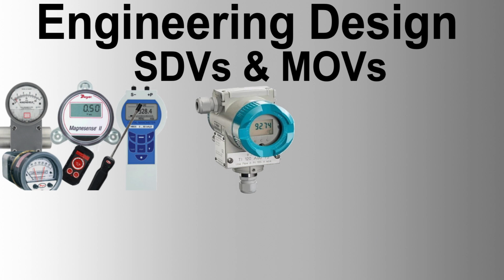Electric valve actuator MOV shall be provided with a smart intelligent actuator with a 2-wire communication network where specified. The intelligent actuator shall be equipped with isolator switches that isolate the actuator while permitting maintenance. Each MOV employs a field unit connected to the master station located in the control room through a 2-wire communication system. The master station shall be connected to the control system through redundant communication.